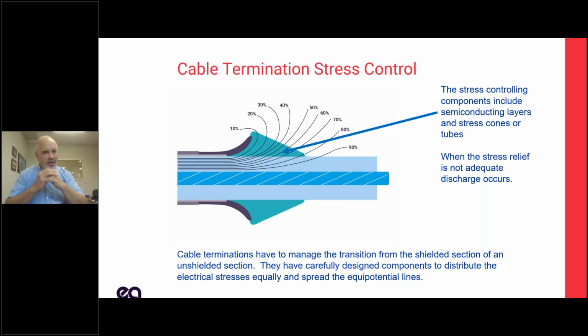And so what we're trying to do is keep those lines, once they're out in the air, as far apart as we can, or far apart enough so that the air doesn't break down. And that's really important. This is where most cable failures occur, in these terminations.